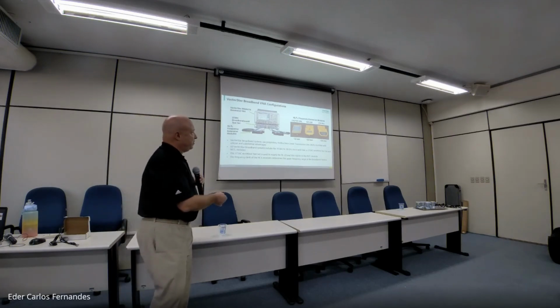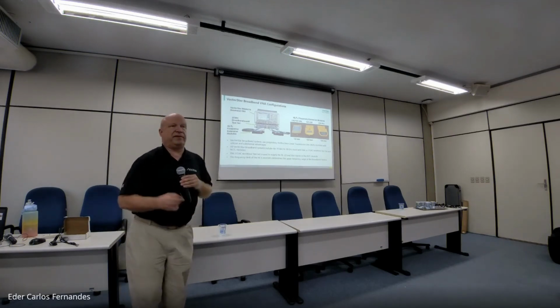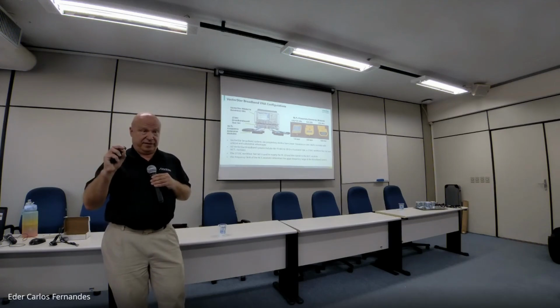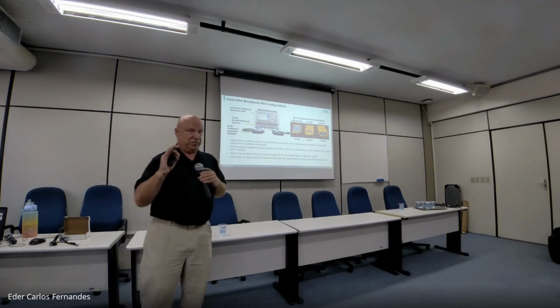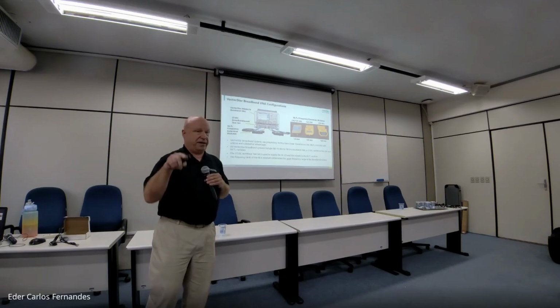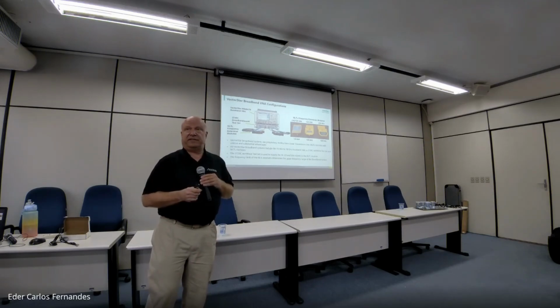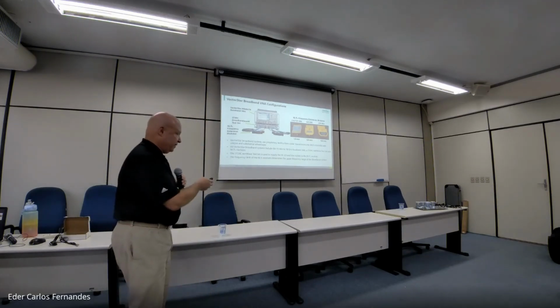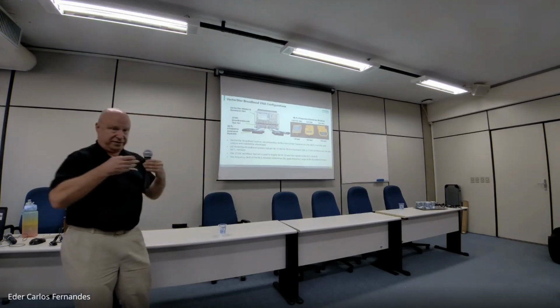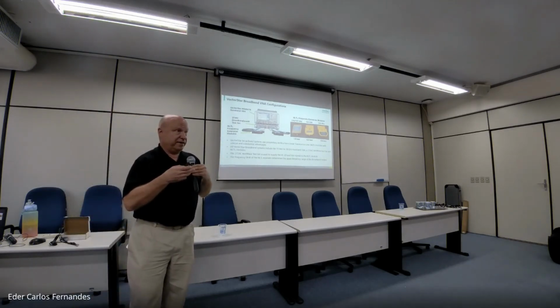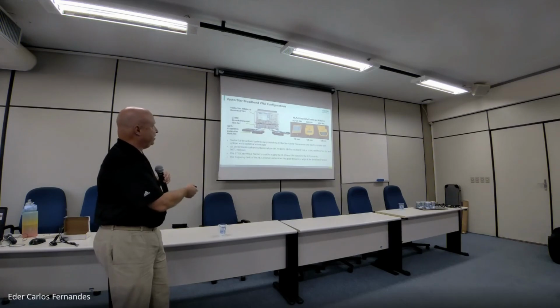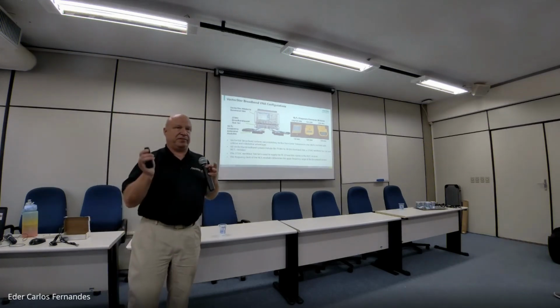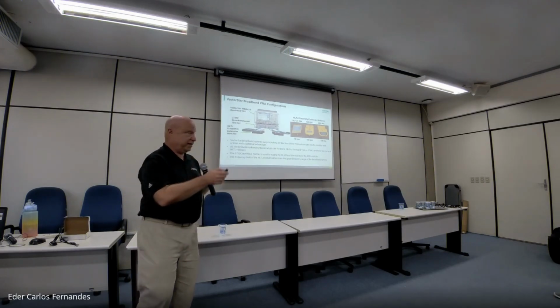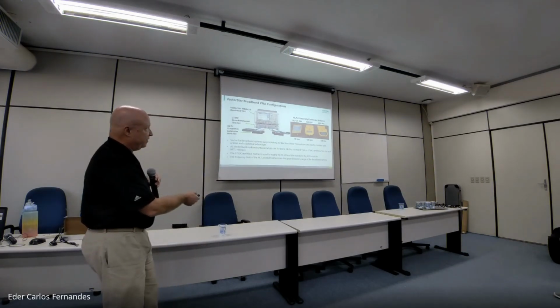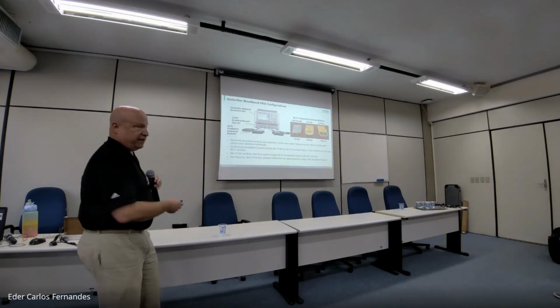But the 220 gigahertz is a 0.6 millimeter coaxial pin. It's like a coaxial waveguide, actually. It doesn't have an outside threading. So the way it works is we have a pin and a socket system, 0.6 millimeter, but it's inside a waveguide flange. So you'll see the alignment pins here that resemble a waveguide. And your first thought might be, oh, it's a waveguide system. No, there's actually a pin inside the small little opening in the front of the module that's 0.6 millimeter.